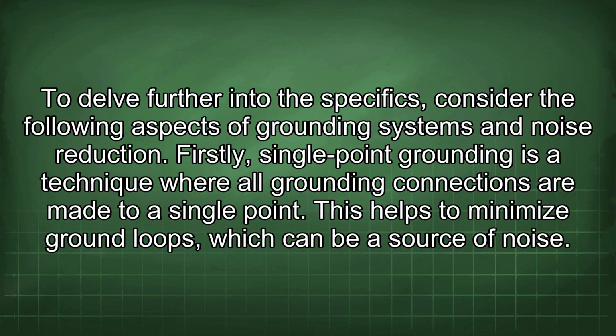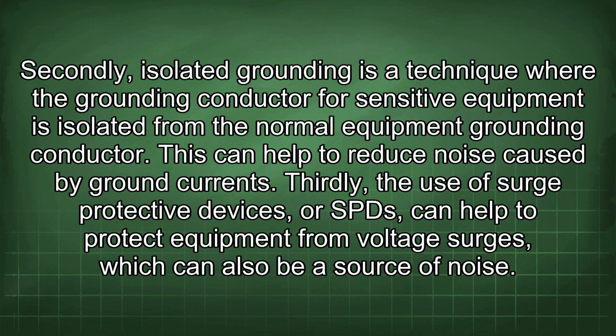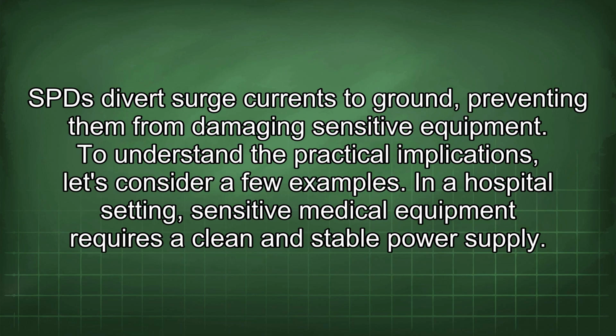To delve further into the specifics, consider the following aspects of grounding systems and noise reduction. Firstly, single-point grounding is a technique where all grounding connections are made to a single point. This helps to minimize ground loops, which can be a source of noise. Secondly, isolated grounding is a technique where the grounding conductor for sensitive equipment is isolated from the normal equipment grounding conductor. This can help to reduce noise caused by ground currents. Thirdly, the use of surge protective devices, or SPDs, can help to protect equipment from voltage surges, which can also be a source of noise. SPDs divert surge currents to ground, preventing them from damaging sensitive equipment.